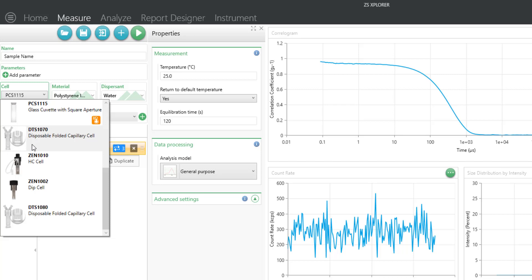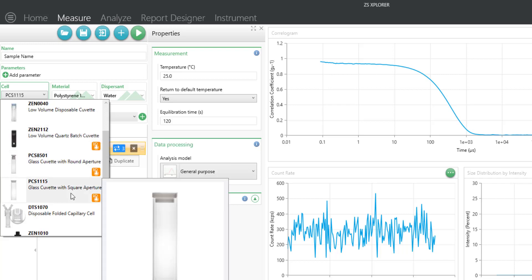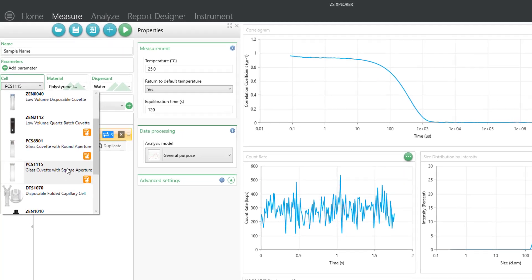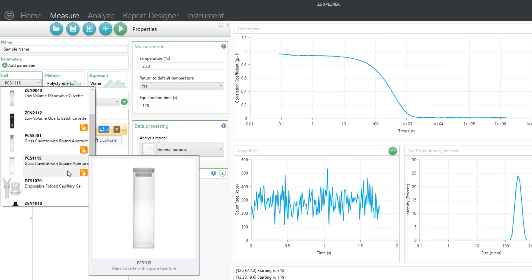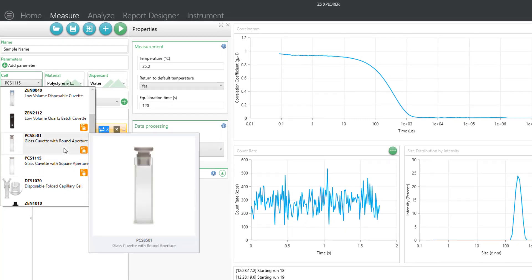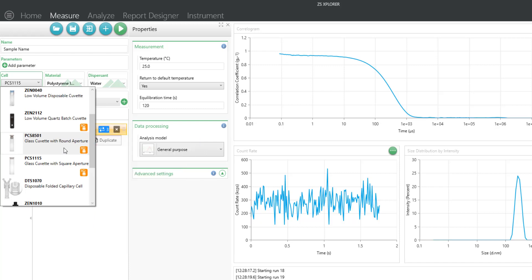Now let's say you're using a sample that's not compatible with plastic such as polycarbonate or polystyrene, then you might want to use one of the glass cuvettes such as the PCS8501. These are reusable, can be cleaned, and are compatible with many organic solvents.